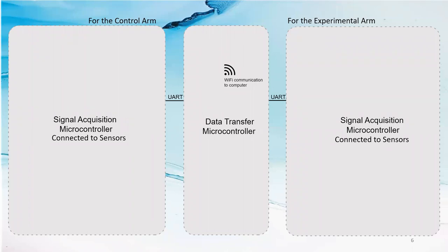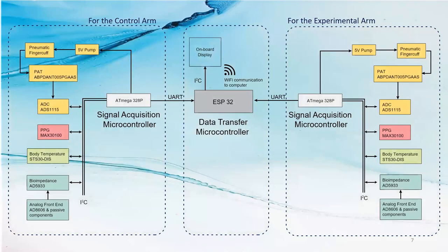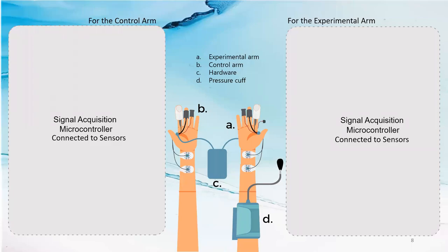The main system can be split into three separate components: one data transmission microcontroller and two signal acquisition subsystems. Each of these signal acquisition subsystems contains a set of sensors — a bioimpedance sensor, a temperature sensor, a blood oxygen level sensor for measuring the PPG, and a pressure sensor. These two systems will be connected to the two arms, using one arm as a control arm and the other as an experimental arm, where blood flow is restricted for a short time to test the endothelial function.